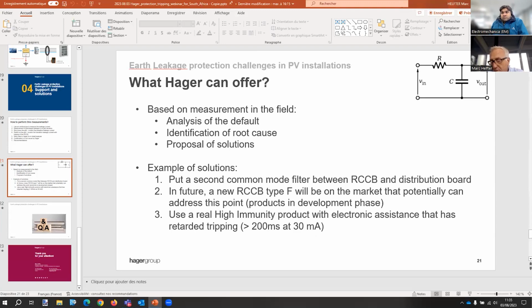I guess, and again, we have to confirm this with some measurements. There is a transition when the grid comes back. There is some transition current that generates this leakage, and the filter embedded in the inverter is doing its job. And when it does its job, the RCCB trips. That's the reason. Okay.